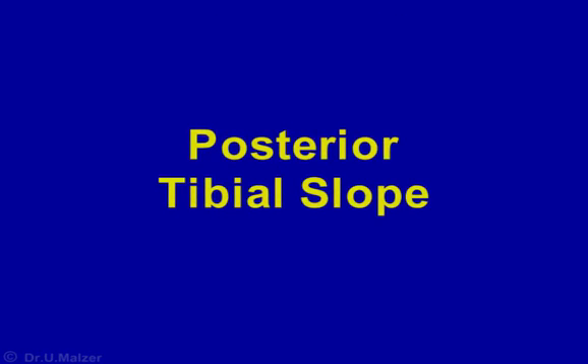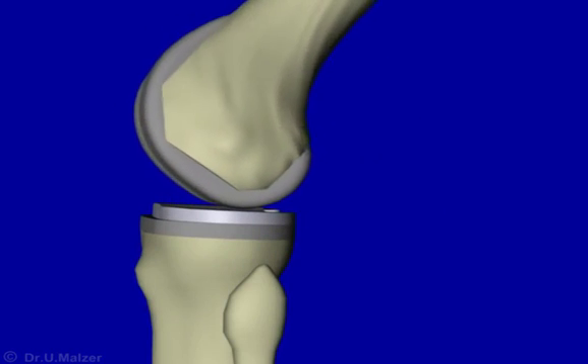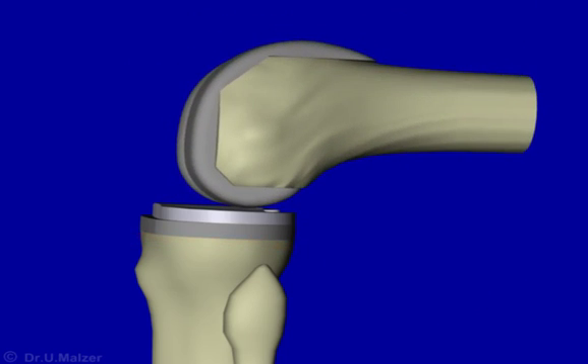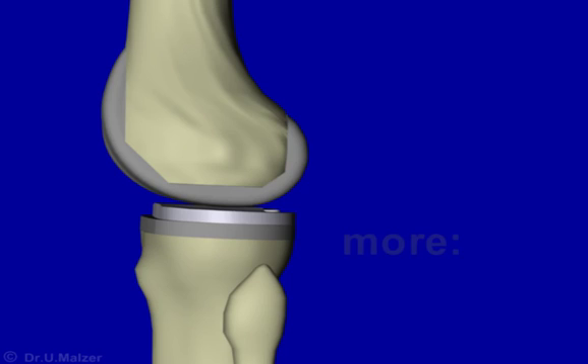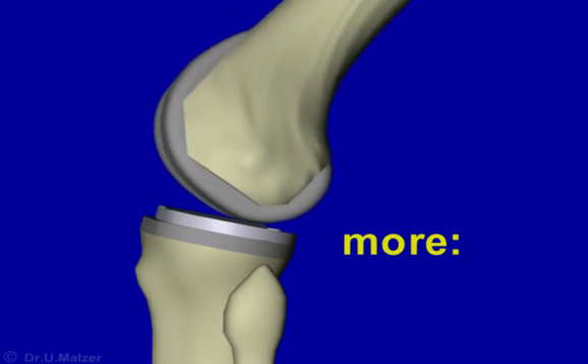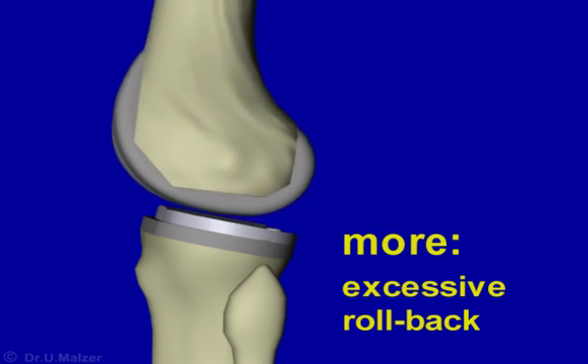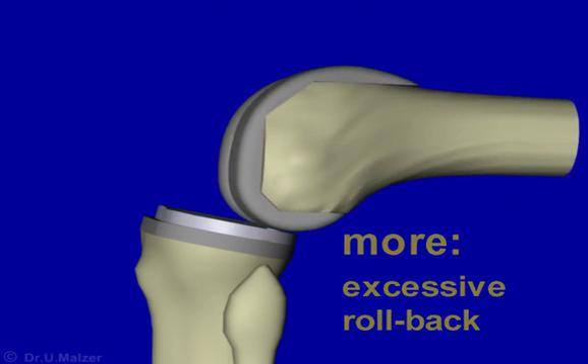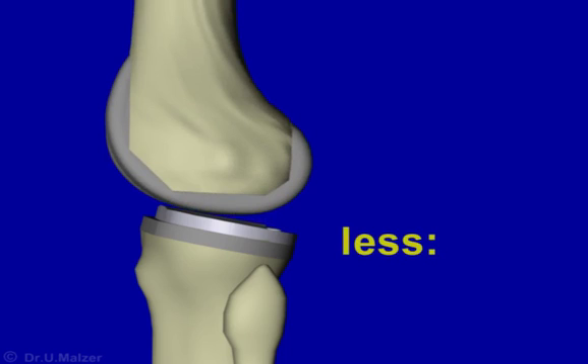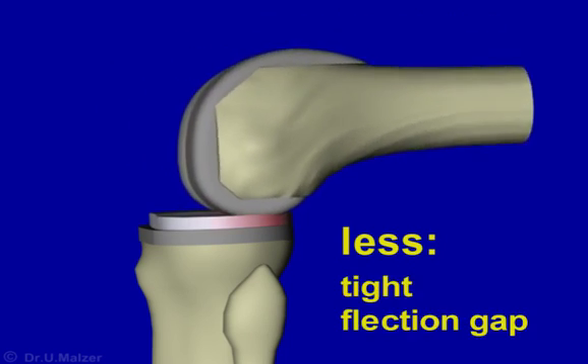The posterior slope of the tibial plateau governs the width of the flexion gap. Normally, the slope will be about five to seven degrees, and the tibial component should be inserted with the same amount of inclination. If the slope is too steep, the knee will be unstable in flexion with increased rollback of the femoral component, leading to excessive stress and increased wear of the posterior part of the insert. If the slope is not steep enough, the knee will be tight with a flexion deficit, and in this case too the polyethylene insert will be subject to increased stress.